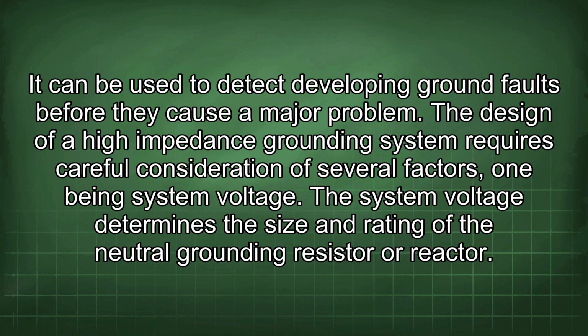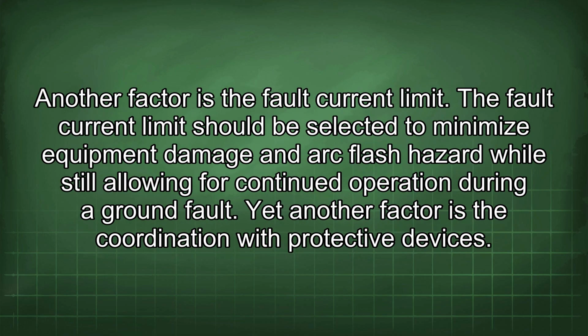The design of a high-impedance grounding system requires careful consideration of several factors, one being system voltage. The system voltage determines the size and rating of the neutral grounding resistor or reactor. Another factor is the fault current limit. The fault current limit should be selected to minimize equipment damage and arc flash hazard while still allowing for continued operation during a ground fault.